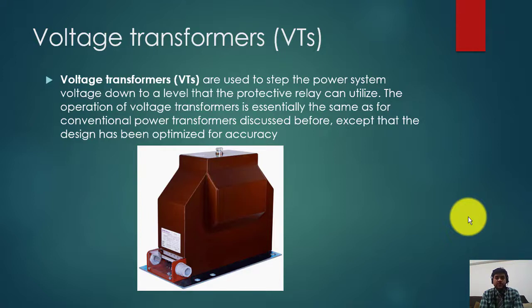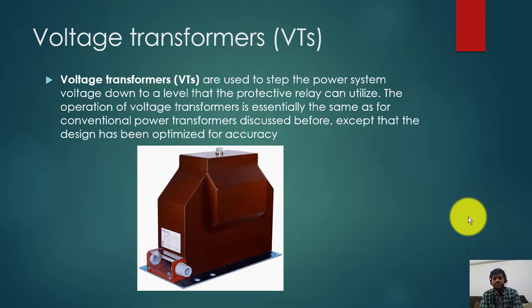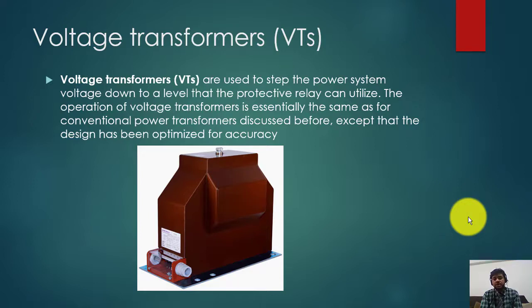For example, if the primary voltage is 11 kV or 132 kV, this voltage cannot be connected directly to the metering system or to distance relays. So you have to step it down. A step-down transformer will reduce the voltage from 132 kV to 110 volts or 100 volts at the secondary side, which is then connected to a relay.